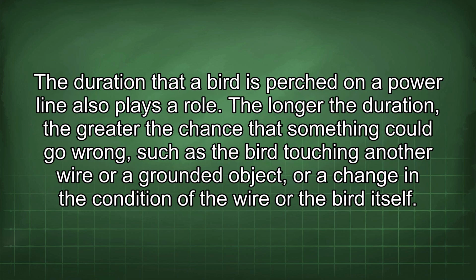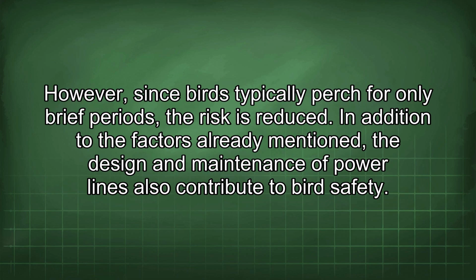The duration that a bird is perched on a power line also plays a role. The longer the duration, the greater the chance that something could go wrong, such as the bird touching another wire or a grounded object, or a change in the condition of the wire or the bird itself. However, since birds typically perch for only brief periods, the risk is reduced. In addition to the factors already mentioned, the design and maintenance of power lines also contribute to bird safety.